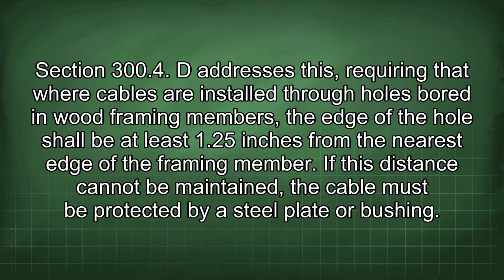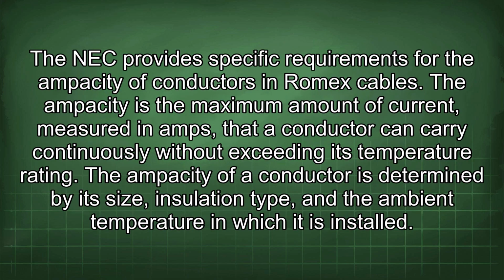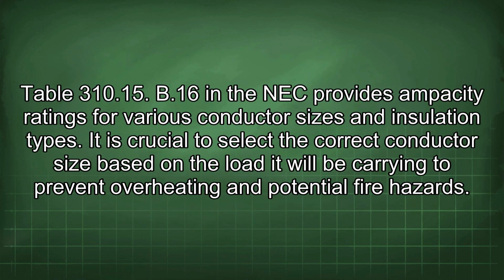If this distance cannot be maintained, the cable must be protected by a steel plate or bushing. The NEC provides specific requirements for the ampacity of conductors in Romex cables. The ampacity is the maximum amount of current, measured in amps, that a conductor can carry continuously without exceeding its temperature rating. The ampacity of a conductor is determined by its size, insulation type, and the ambient temperature in which it is installed. Table 310.15.